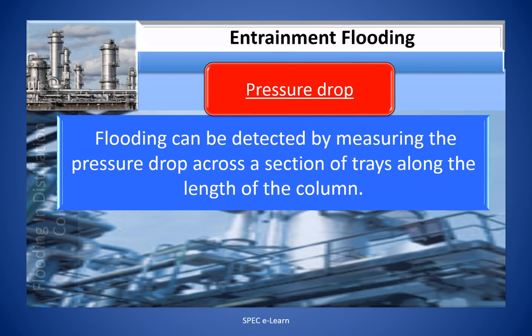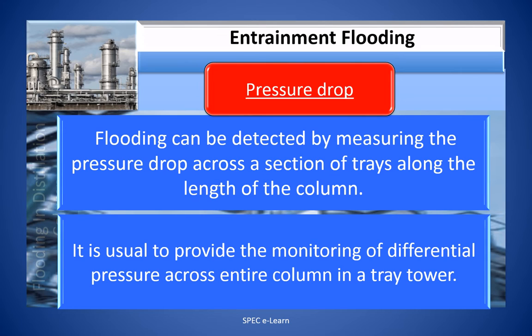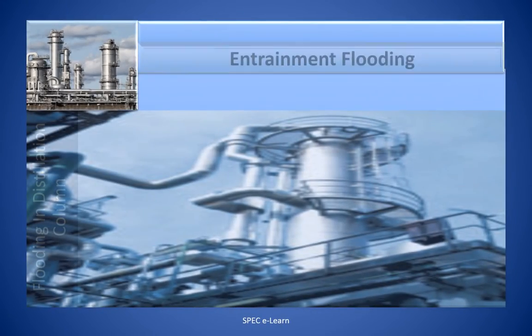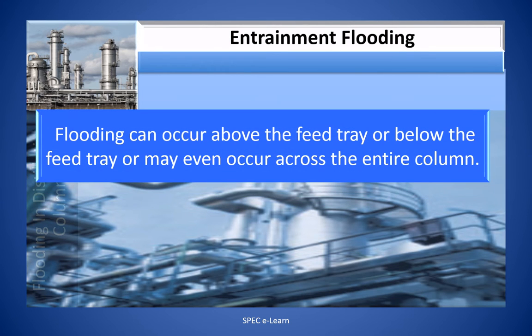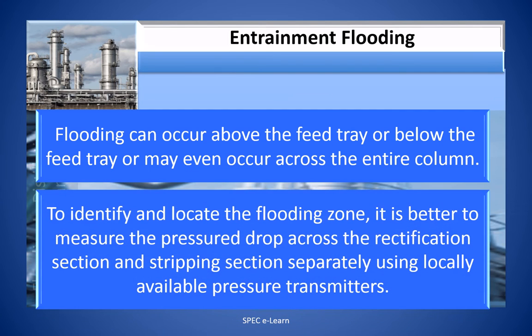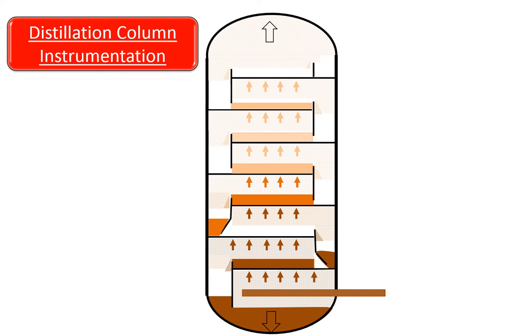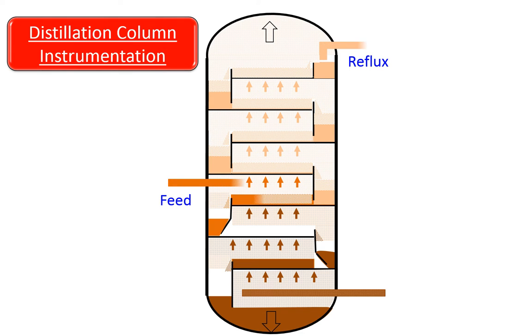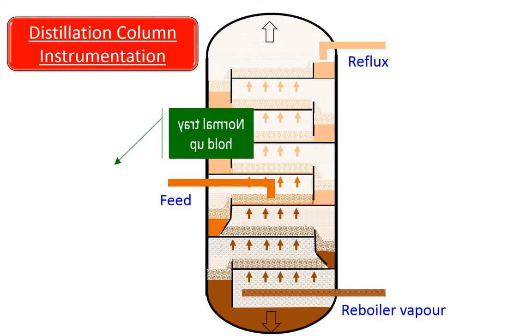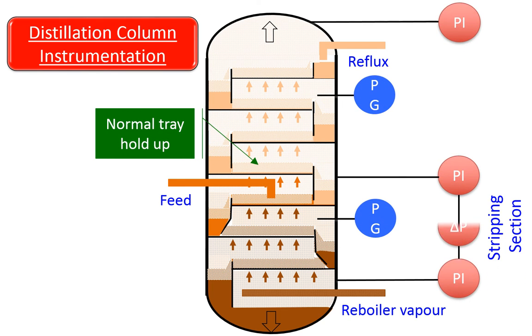Flooding can be detected by measuring the pressure drop across a section of trays along the length of the column — the differential pressure across the column in a tray tower. Flooding can occur above the feed tray, below the feed tray, or across the entire column. To identify and locate the flooding zone, it is better to measure the pressure drop across the rectification section and stripping section separately using locally available pressure transmitters. This figure illustrates a distillation column working under normal condition: when vapor and liquid loads are within the design limit, the differential pressure as indicated by the differential pressure transmitter will be normal.